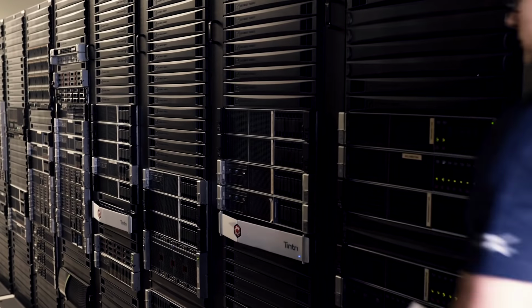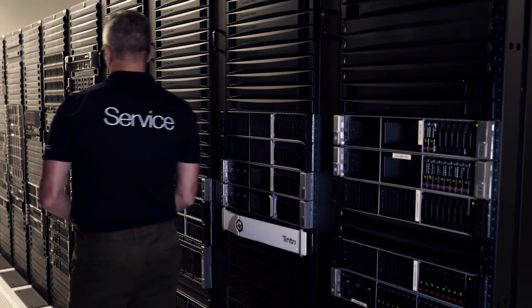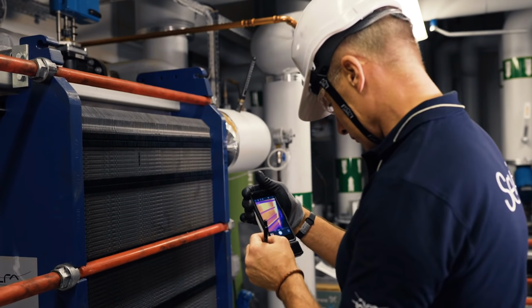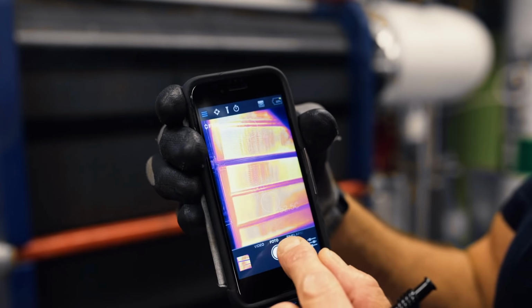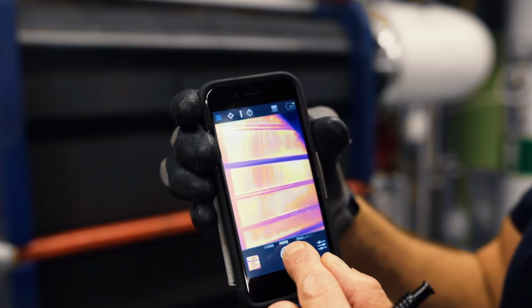Avoiding fouling in heat exchangers in the data centers will improve their sustainability, since fouling leads to a decrease in heat transfer. Typical causes of fouling are related to process conditions, for example running the heat exchanger at too low flows, too high temperatures, or not having filters installed, but it's also related to the composition of the medium, like having hard water, dirty water, or small particles present in the water.